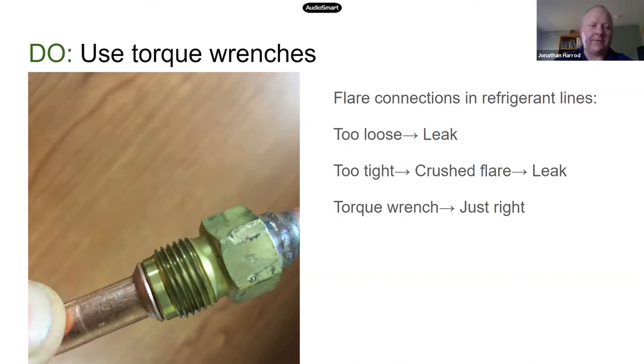There are different torque settings needed for different types of tubing. The smaller tubing that we use, the quarter inch tubing, only needs about 13 foot-pounds of torque. But the larger tubing, the 5/8 tubing, needs 50 pounds of torque.